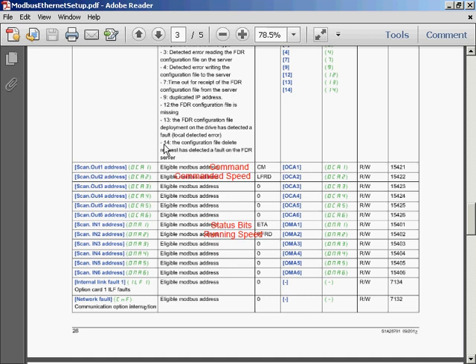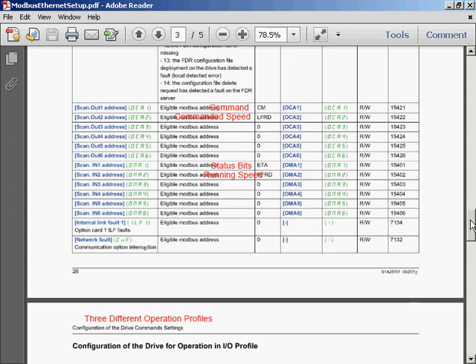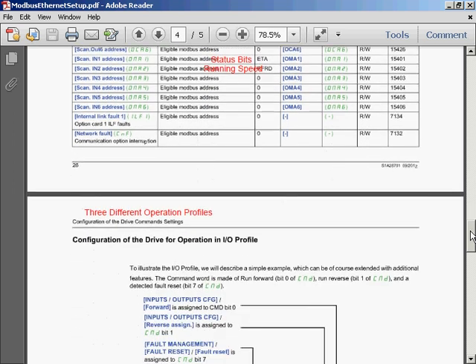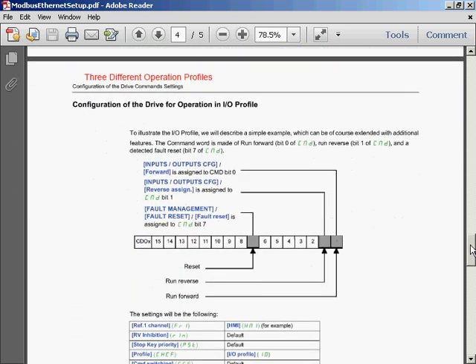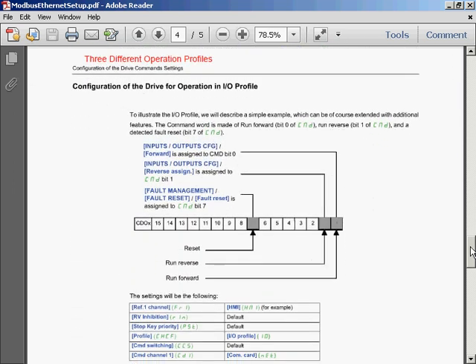This is the default where the first output from the PLC is the control word. And the second output is the commanded speed. And then we've got the two inputs monitoring the status and the current running speed of the drive. As I scroll down further through the document, I've grabbed excerpts out of the document. But there are three different operation profiles that we can set up in the drive.